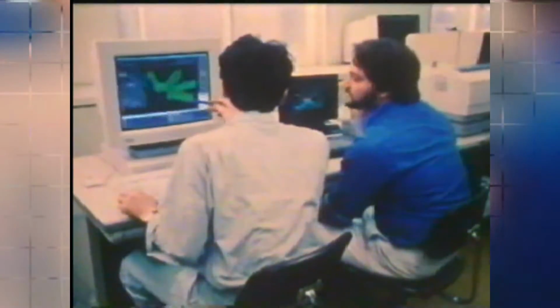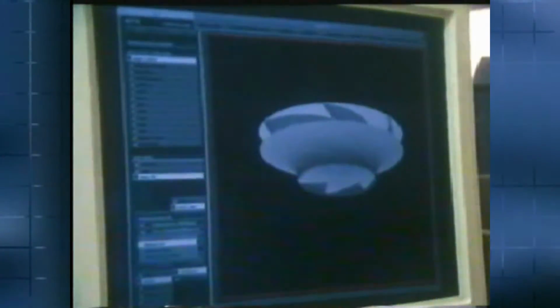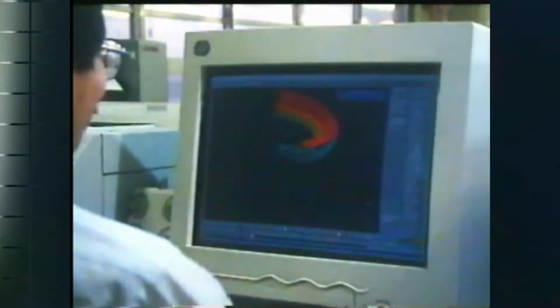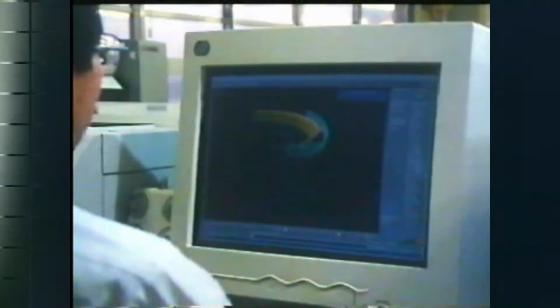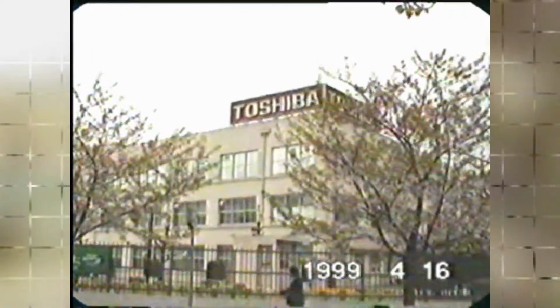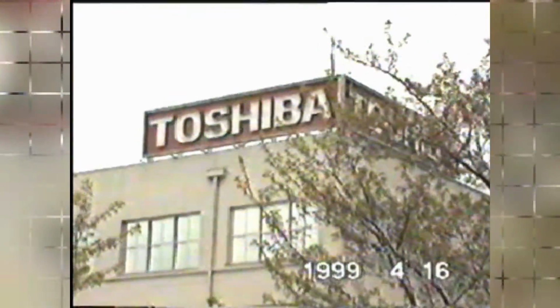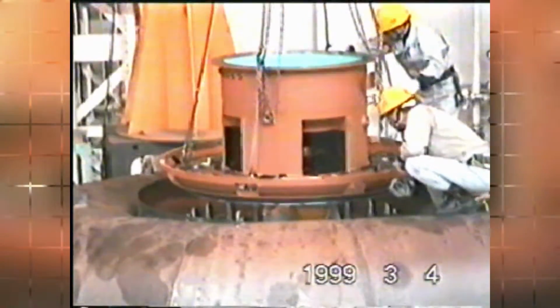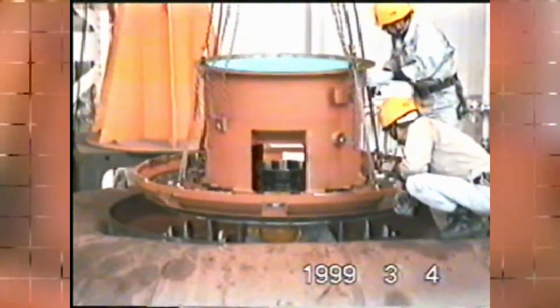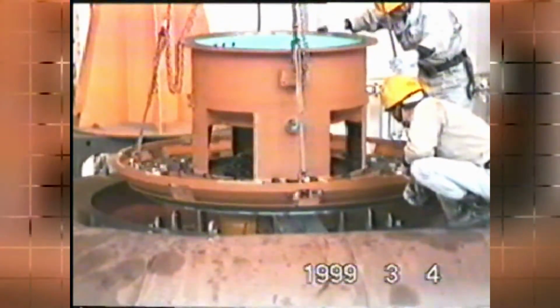Detailed drawings, literature, and instructions before proceeding with the manufacture of the equipment, Toshiba Engineering Corporation performed the design data, design analysis, the design calculations in typewritten book-bound form, detailed specifications, general assembly drawings and details, and manufacturer's descriptive literature to demonstrate fully that all parts will conform with the requirements. Each operational unit is fully assembled as far as practicable in the workshop and measured to ensure that all component parts are properly manufactured and that all design dimensions, tolerances, and clearances have been obtained.